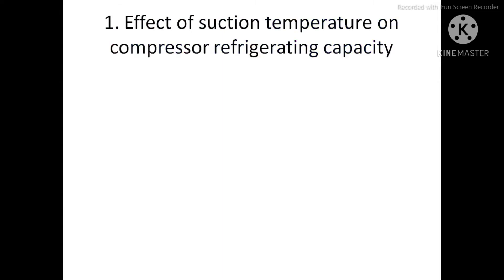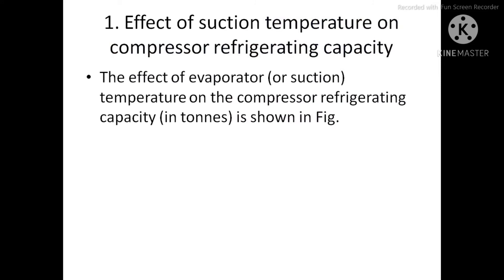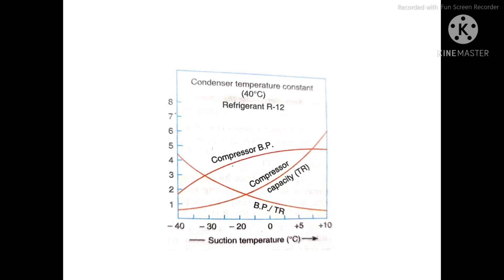First, let's look at the effect of suction temperature on compressor refrigerating capacity. The performance curves for the reciprocating compressor are shown in the figure, with suction or evaporator temperature in degrees Celsius on the x-axis. Three performance parameters are plotted: compressor capacity, compressor brake power, and brake power per ton of refrigeration.